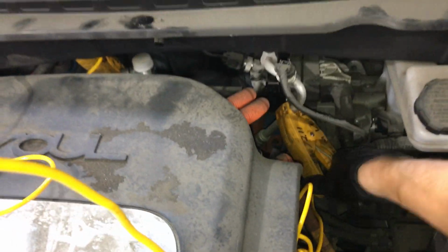We're gonna look at the liquid line temperature, so let me clamp it right here going in. Let's see what our drop is, what's going on inside if we're getting a drop. 137 degrees. 137. And I don't think I could grab... no, they got that glued in there, I can't grab that other one.